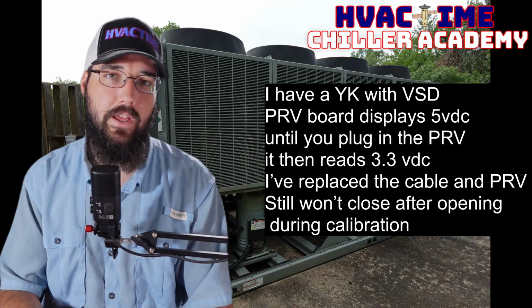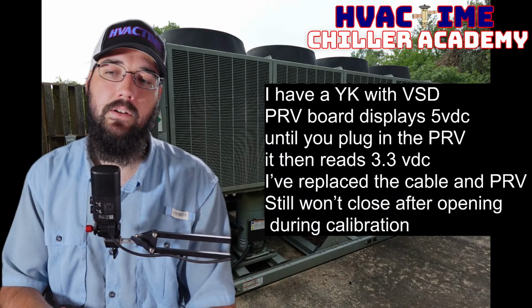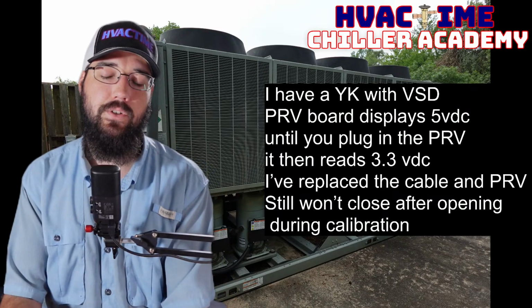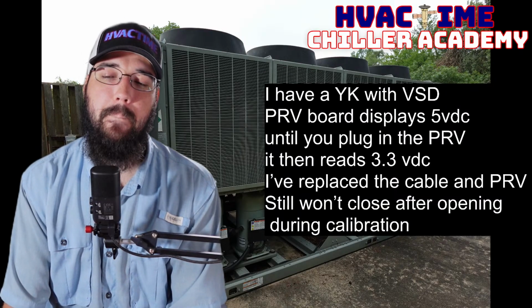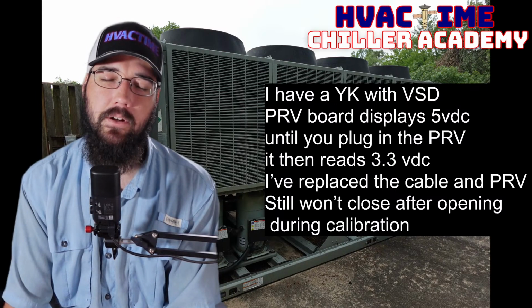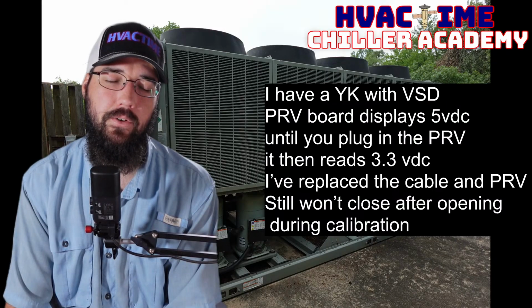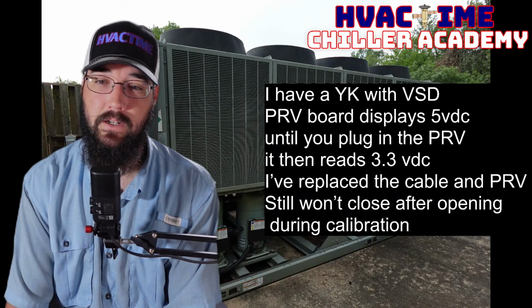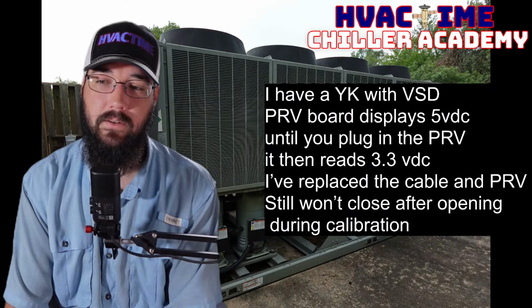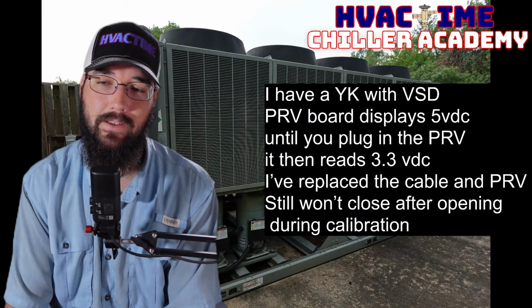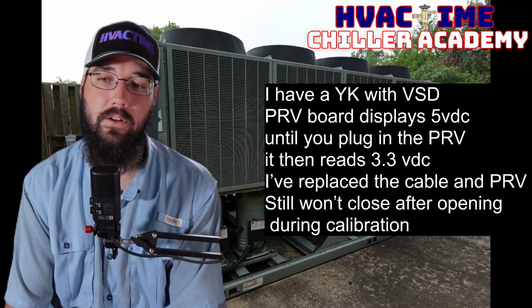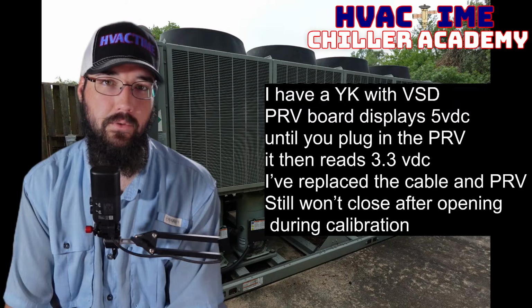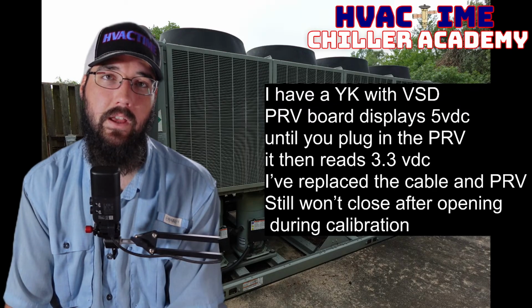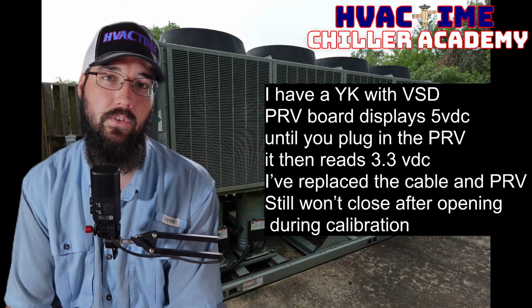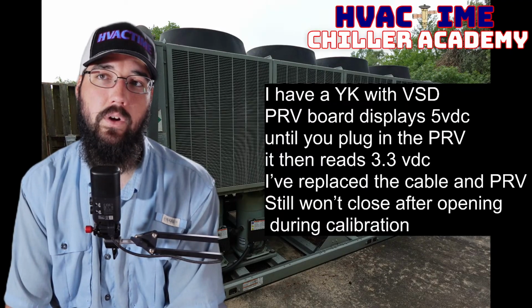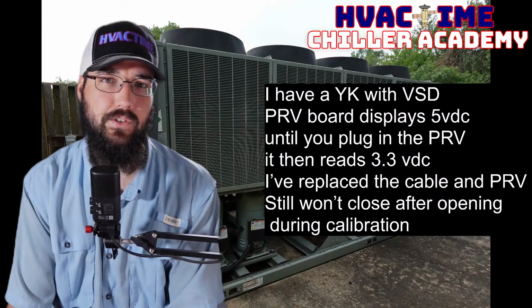Like, you're confident in the cabling, you're confident in the PRV itself, which I really wonder. I'm getting hung up on the way you structured it, whether you're talking about the PRV sensor or the PRV actuator. Because if we're talking about the PRV sensor, the reason that's hanging me up is that 3.3 VDC when it's plugged in, depending on what position the rheostat's in, would be normal, because that rheostat is causing a voltage drop, which correlates to a specific ohm value, which is what the panel is using to confirm position.